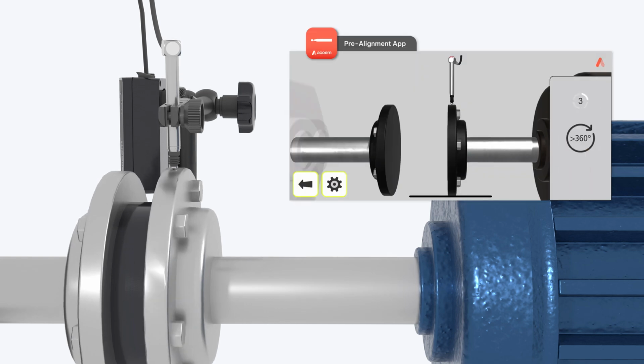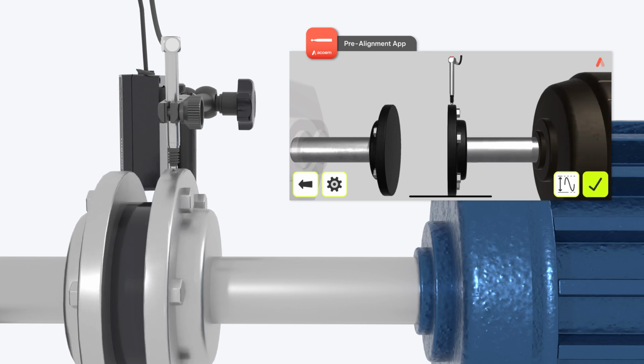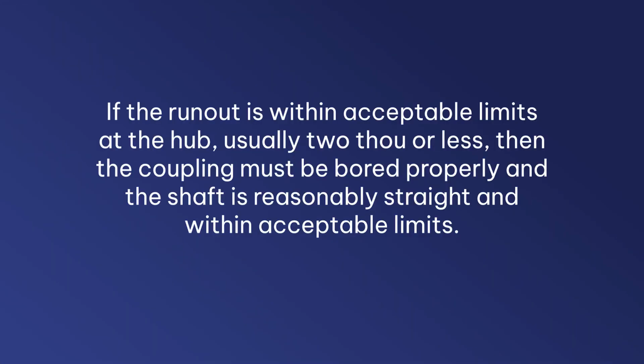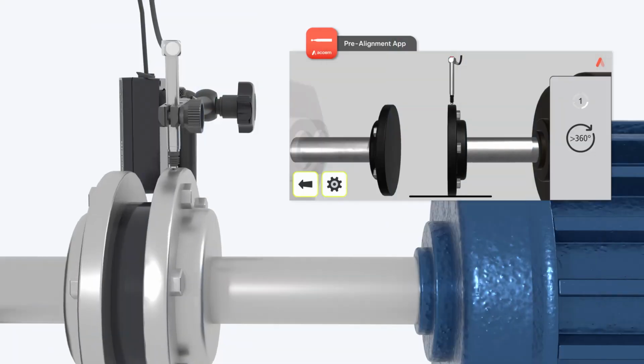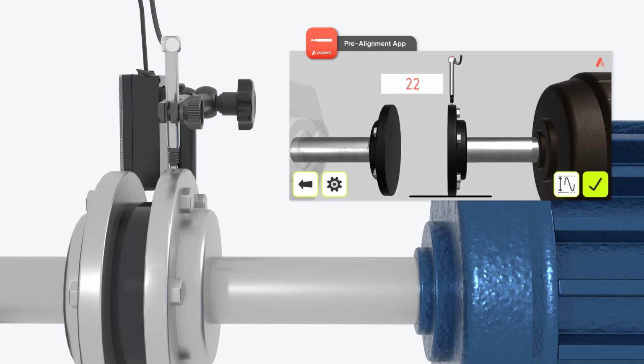As the shaft rotates, the probe determines the total amount of runout. The pre-alignment application takes the difference of the minimum and maximum values to calculate the total runout present. If the runout is within acceptable limits at the hub, usually 2 thou or less, then the coupling must be bored properly and the shaft is reasonably straight and within acceptable limits. In this case, the probe is indicating excessive runout of 22 thou.